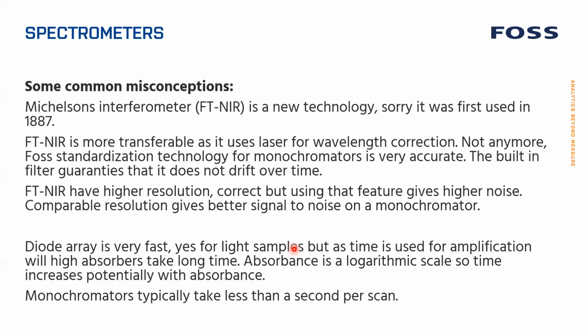Also, there's the claim about the FT-NIR being more transferable, as it uses a laser for wavelength correction. That is true. It's very transferable, but the monochromators we have and the system for standardization we have for our monochromators, it's very accurate. So the built-in filter guarantees that it doesn't drift over time. And also this with the FT-NIR having a higher resolution. That is correct, but if you use that feature, you will also get a higher noise. So if you look at what we are doing and how we use our instruments, in general, our instrument is better for quantitative measurements than an FT-NIR is.